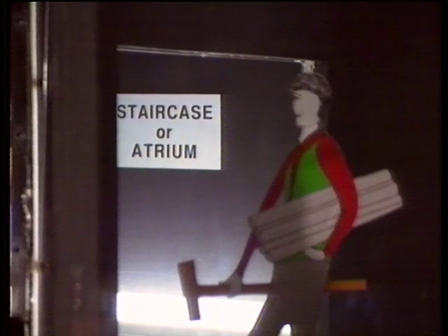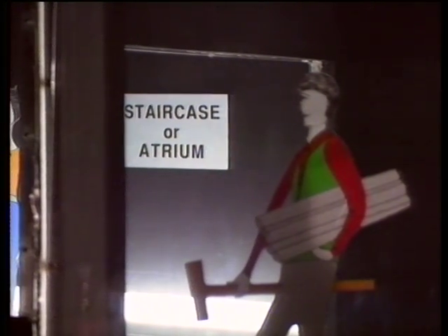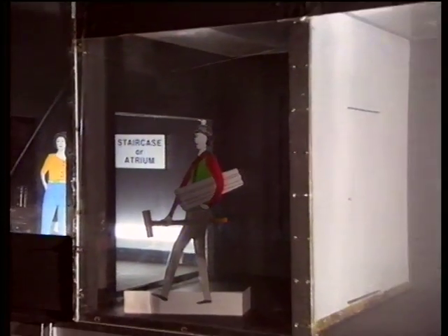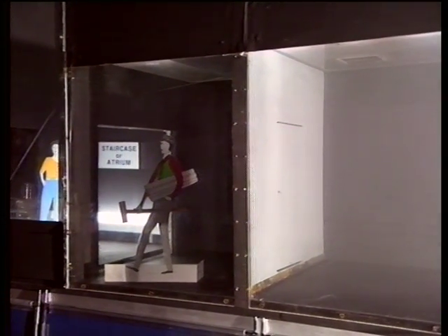Because no smoke enters the lobby or staircase shaft, these form a place of safety, which people from the rest of the building can use as an escape route. This method is relatively simple and inexpensive to implement, and it's reliable. The main proviso is that the doors are smoke sealed.